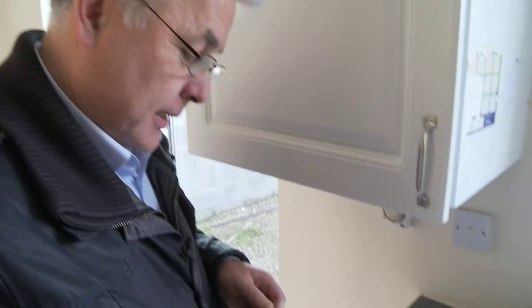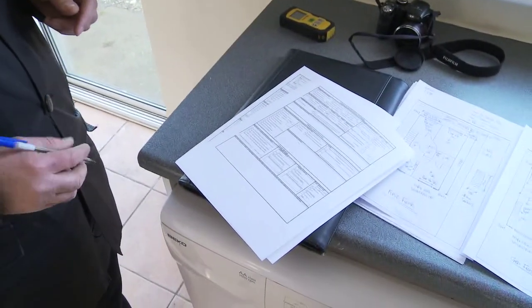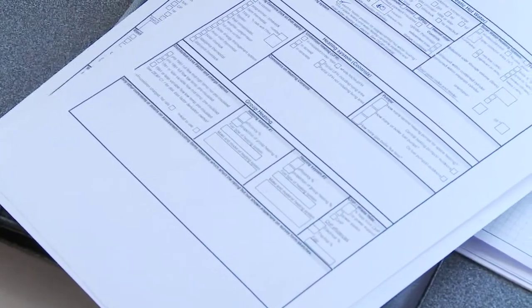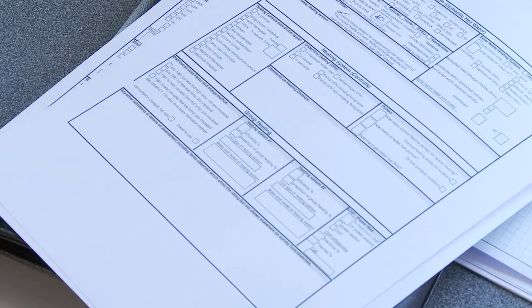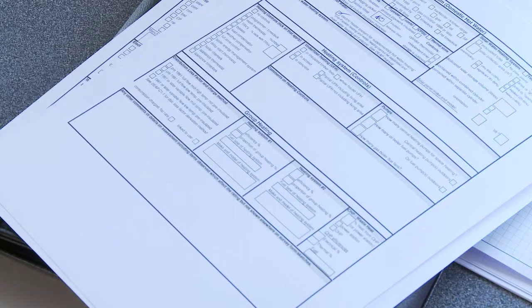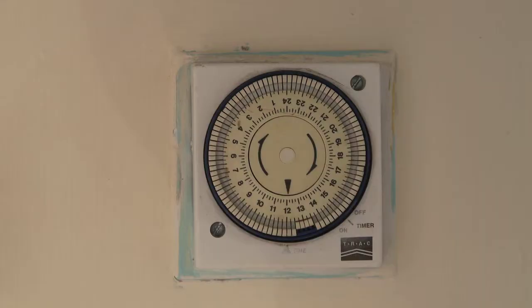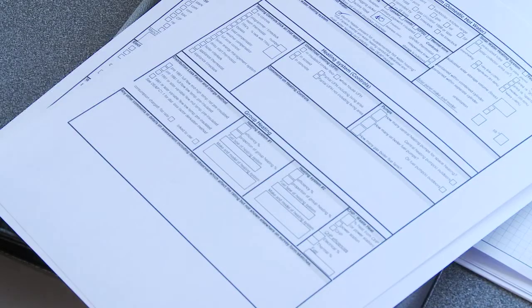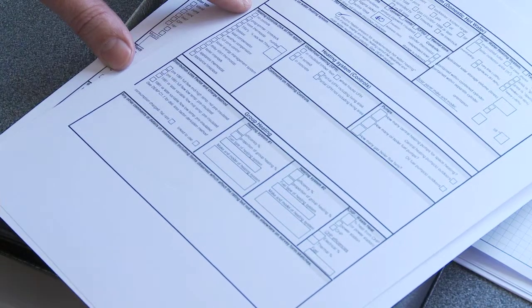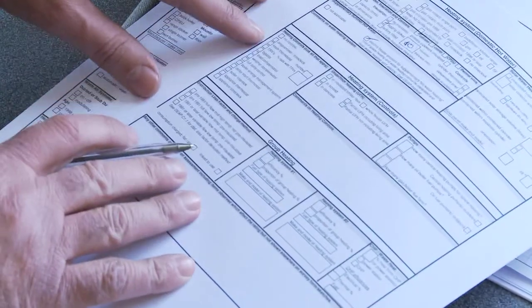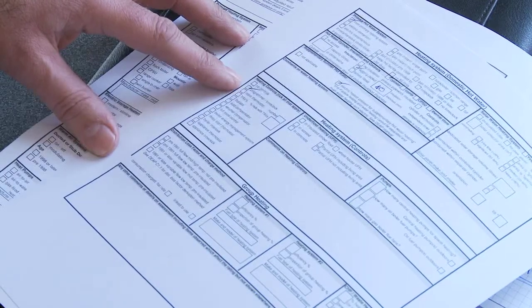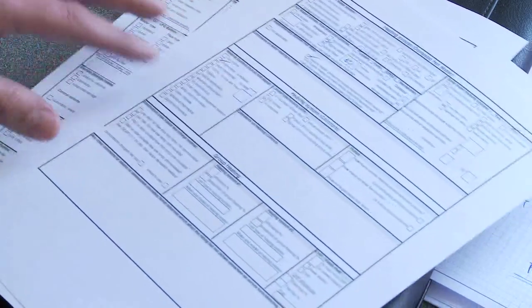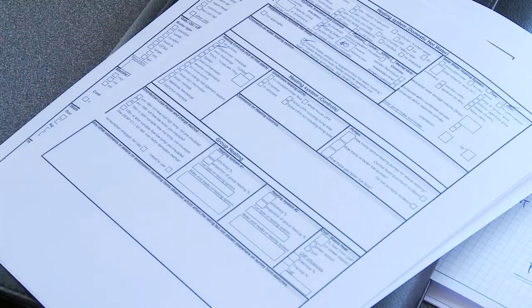And then the last thing we look at are the heating controls. Now, we've had a look around and we can see that there are no TRV valves on the radiators. And in fact, the only controls that we do have are the timer control that was positioned directly below the boiler. So from our heating controls point of view, what we have is just the second one down, which is a programmer stroke time clock. And we tick that box. And then we don't have any underfloor heating, so we can ignore that.